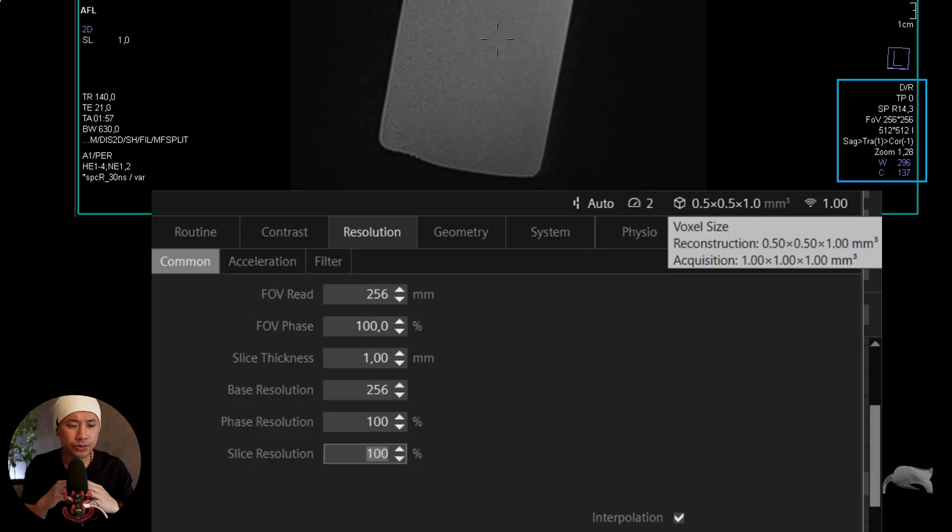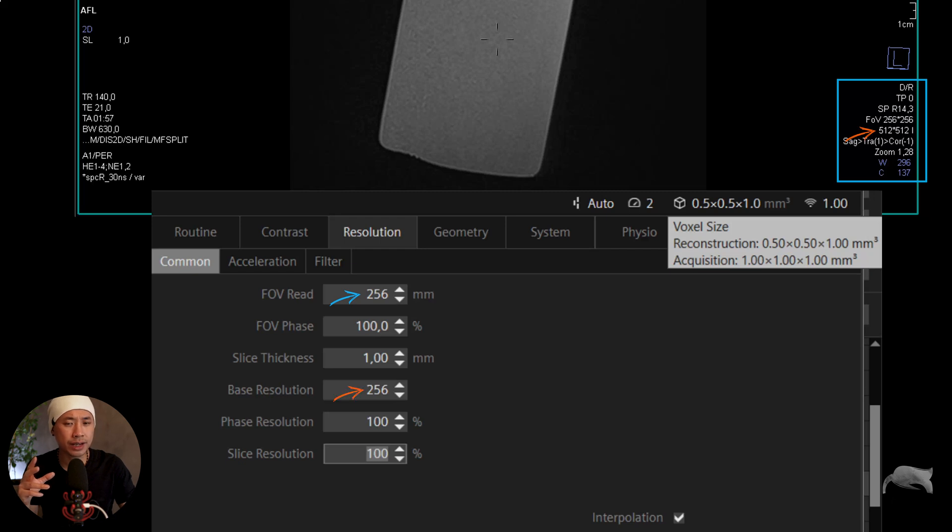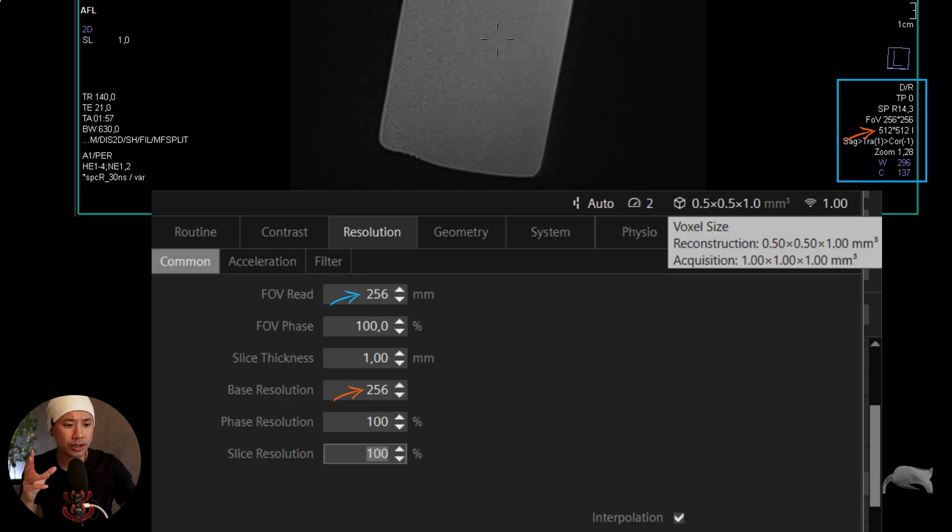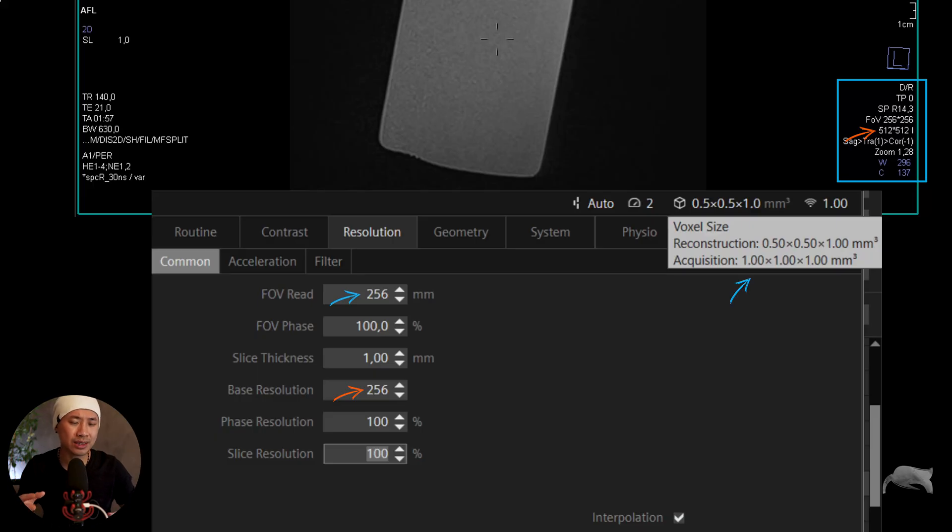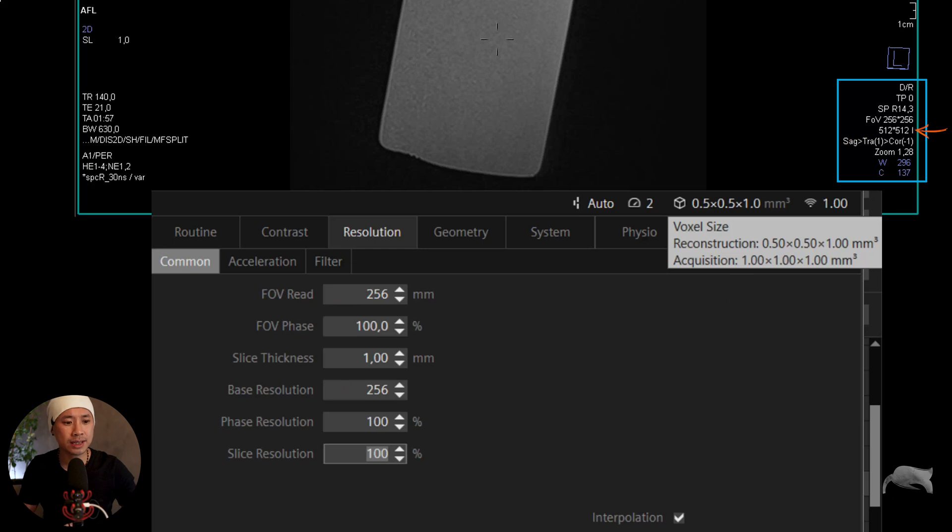In the next corner right here, we're going to talk about resolution. So the field of view I have here is 256 as it says there, and 256 by 256. And then you can see why is the matrix 512 but it says 256 right there? Strange, right? It's not that kind of strange because you're using interpolation mode, which means you are doubling up the matrix. So if you do the calculation, 256 divided by 256 is one millimeter, and then you're using interpolation function so you now get 0.5 on the reconstructions on the phase and the frequency. So at least if they're interpolated, you will see with an 'i' here - it means that it's interpolated.